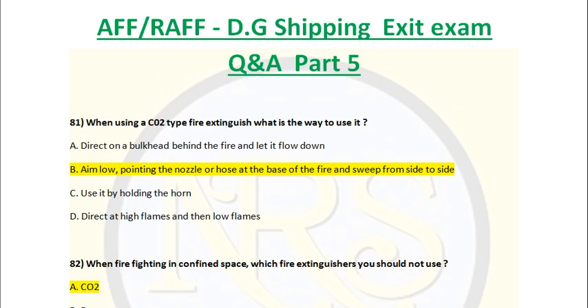A CO2 extinguisher is heavier than air, but it is not a liquid, it's a gaseous compound. It can fly over with the air, and it has very poor cooling effect. It works only on the principle of smothering, removal of oxygen from the fire. So you have to aim as low as possible to the base of the fire to extinguish it, and sweep left and right, up and down, covering the whole area to prevent reignition, since it has poor cooling effect and only cuts off the oxygen.